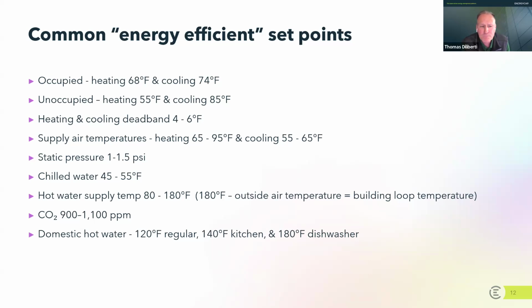CO2 levels, if you were with us the last webinar, we talked about that quite a bit, but the most common range is between 900 and 1100 parts per million. Again, ambient CO2 is about 400, and usually when you get roughly 1,000 more than that, they want you to ventilate more. So that's what you see in the sensors.